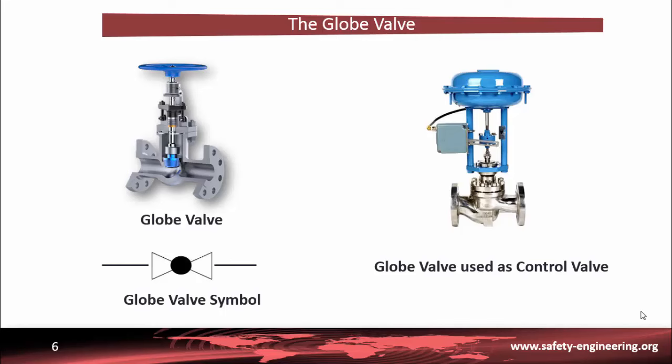Globe valves also have a lower chance of damage to the seat or valve plug from the fluid, even if the seat is in a partially open position. The advantages are good shutoff capability as well as excellent and accurate throttling ability. For high pressure systems, the globe valve is available in T, Y, and angle patterns, each offering unique capabilities. The disadvantages are a higher pressure drop compared to a gate valve, and this valve requires greater force or a larger actuator to seat the valve.